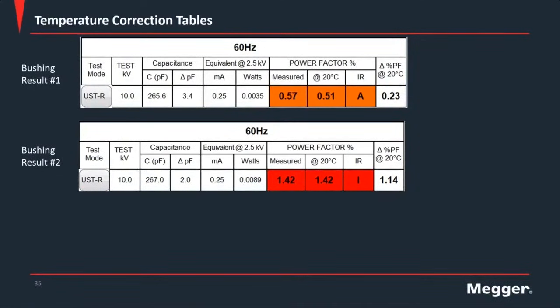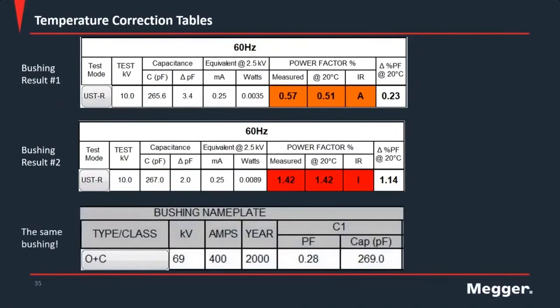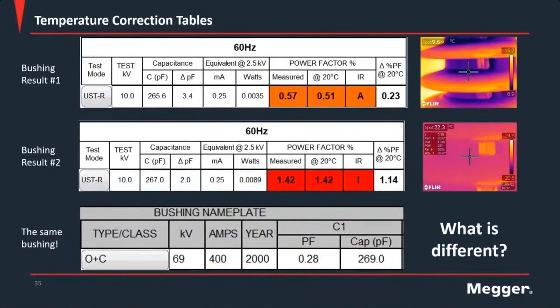So looking at these two bushings, which one would we say is the one that requires more maintenance efforts? And I think we would all agree that it's the second bushing. But it turns out that these bushings are actually the same 69 kV bushing. So what is different? The only thing that was different is the temperature at which the bushing was when the test was performed. One was around 10 degrees C and the other was around 22 degrees.